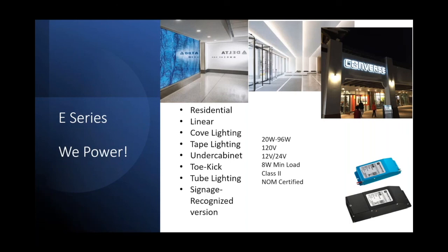The wattage options range between 20 and 96 watts, 120 volt input only. We do offer a 12, 24 volt option, and the minimum load is down to about 8 watts. Dimmable down to 1%. This is a Class 2 rated driver, and it's NOM certified as well, like I just mentioned about the M series.